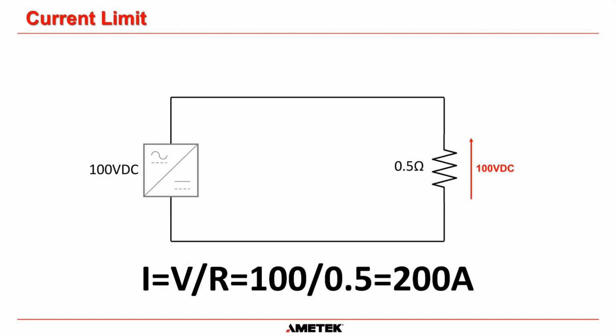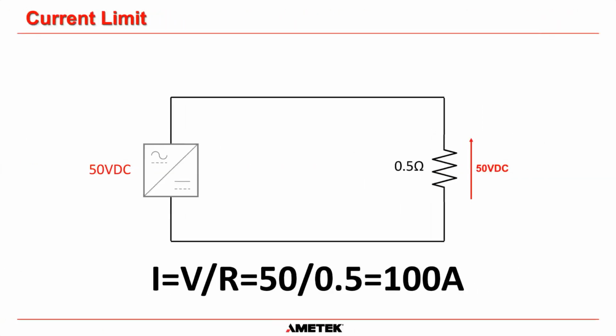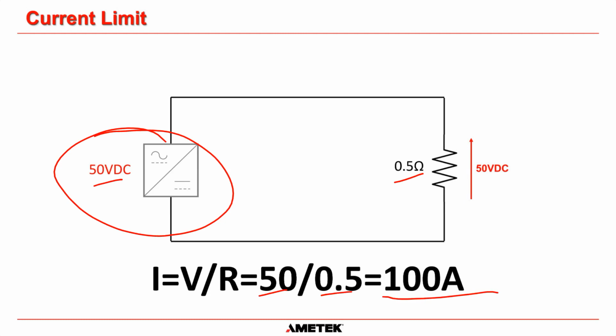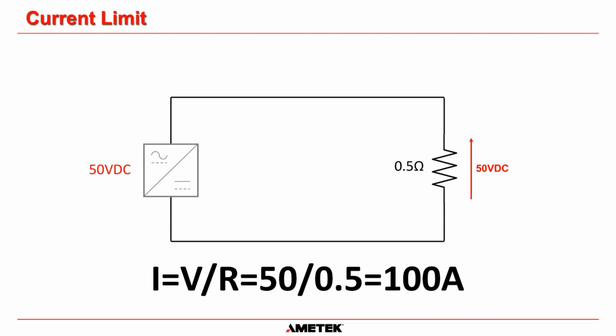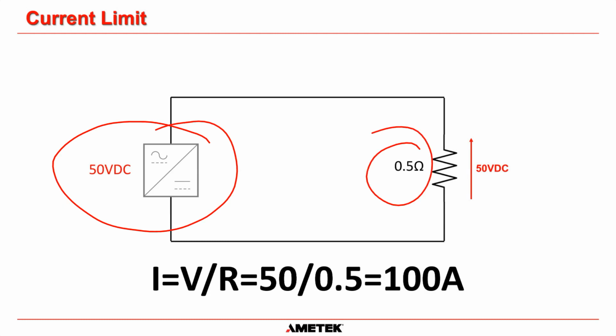So in this situation here, to get this current of 200 amps down to 100 amps, which is the safe rating of that charger, what it would have to do is it would reduce the voltage of the charger down to 50 volts. Once again, if you use Ohm's law, 50 volts divided by this new load of 0.5 ohms, we're back down at 100 amps. Safe. The SCRs are not going to blow up and everything is good. That is how current limit in nearly all chargers works. We are not changing the current, we are changing the voltage, which will then change the current dependent on the resistance of the load circuits.